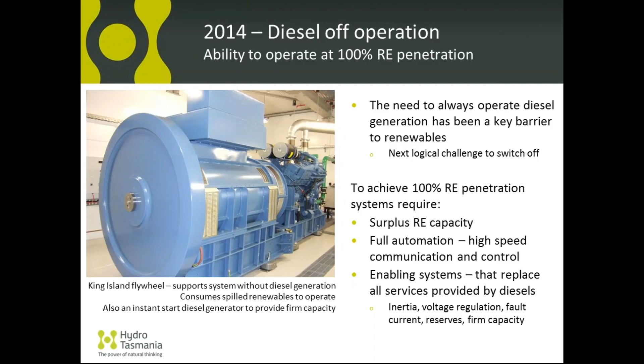So we installed this system for the first time in the world - the renewables drive the big blue flywheel you can see there. It's 4 tons of steel rotating at high speed, meaning we have available at all times a generation unit that can inject power. There's a diesel engine associated with it, but that's only used to start the wheel spinning, then it goes offline, and is only called on if the system needs to inject power for a lengthy period before we can stabilise the network with other diesels if we lose wind or solar for a sustained period.